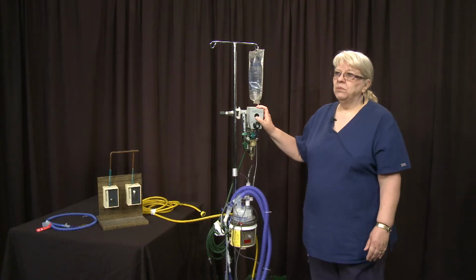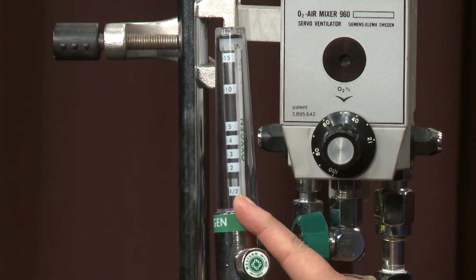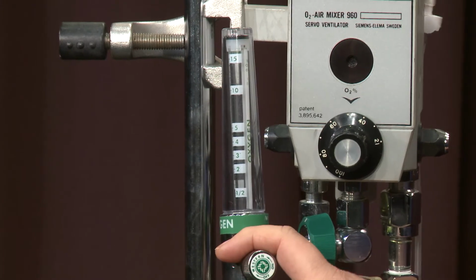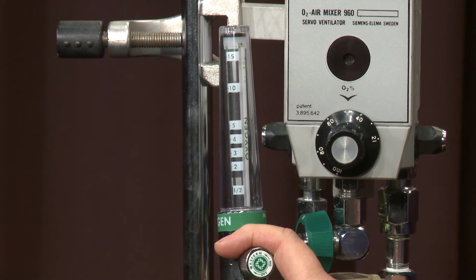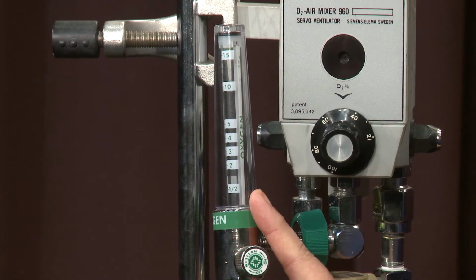After the gas has been blended, the flow comes outside here, and then it can go to one of two types of flow meters. Either a regular flow meter up to about 15 liters per minute, which would be for smaller patients, or I could put a high flow meter on here, which could go up to 40 liters per minute for an adult patient.